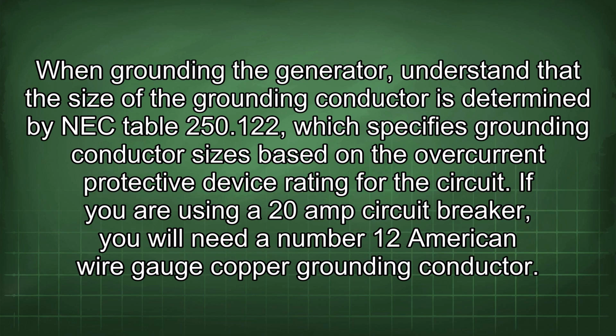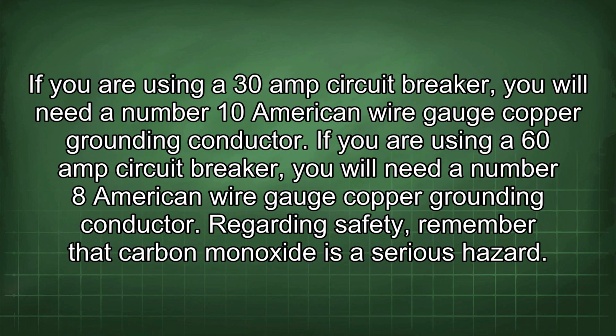When grounding the generator, understand that the size of the grounding conductor is determined by NEC Table 250.122, which specifies grounding conductor sizes based on the overcurrent protective device rating for the circuit. If you are using a 20 amp circuit breaker, you will need a number 12 American wire gauge copper grounding conductor. If you are using a 30 amp circuit breaker, you will need a number 10 American wire gauge copper grounding conductor. If you are using a 60 amp circuit breaker, you will need a number 8 American wire gauge copper grounding conductor.